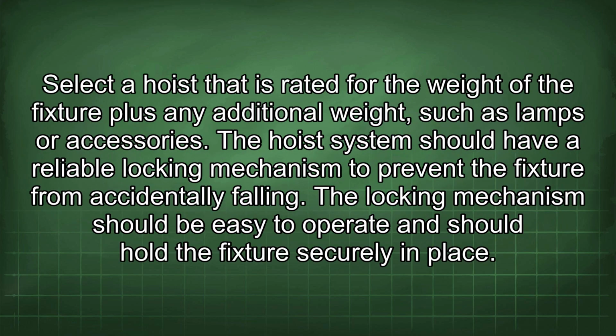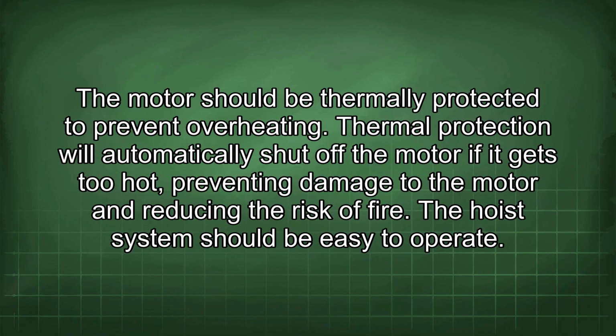When choosing a fixture hoist, consider the maximum weight capacity. Select a hoist that is rated for the weight of the fixture plus any additional weight, such as lamps or accessories. The hoist system should have a reliable locking mechanism to prevent the fixture from accidentally falling. The locking mechanism should be easy to operate and should hold the fixture securely in place. The motor should be thermally protected to prevent overheating. Thermal protection will automatically shut off the motor if it gets too hot, preventing damage to the motor and reducing the risk of fire.